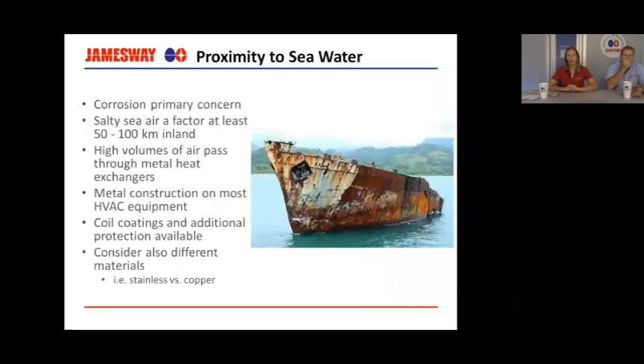Proximity to seawater. Our concern there, of course, is corrosion. And salty sea air can be a factor up to 100 kilometers inland. We have very high volumes of air moving in a hatchery, and those are going through metal heat exchangers, and that's what we don't want to corrode. If you're located in an area like that, what you really want to look for is getting coil coatings to protect your heating coils and your cooling coils. You also want to make sure your HVAC unit has a paint on the outside. It's not a bare metal unit. And then also consider different materials. Does it make sense to go on that upgrade to the stainless steel heating coils instead of a copper heating coil?